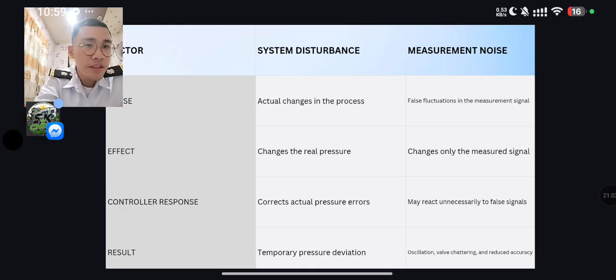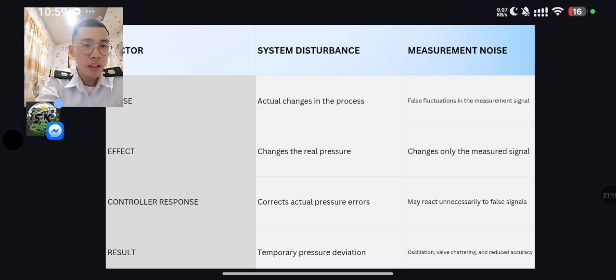On the other hand, measurement noise causes fluctuations in the measurement signal and changes only the measured signal. The controller may react unnecessarily to the false signals. Measurement noise can result in oscillation, valve chattering, and reduced accuracy. The main difference is that disturbances are real process changes, while measurement noise is only an error in the measurement signal.